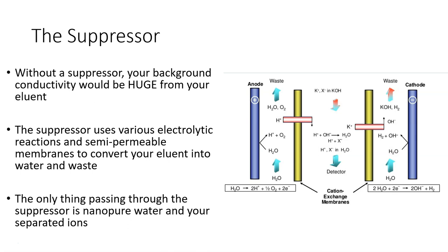Setting your suppressor's current too high can result in seeing no peaks at all, and setting your suppressor's current too low can result in ridiculous looking massive peaks and a ton of background noise. In the end, the only thing that passes through your suppressor is nano pure water and your separated ions, so your conductivity detector can work efficiently.